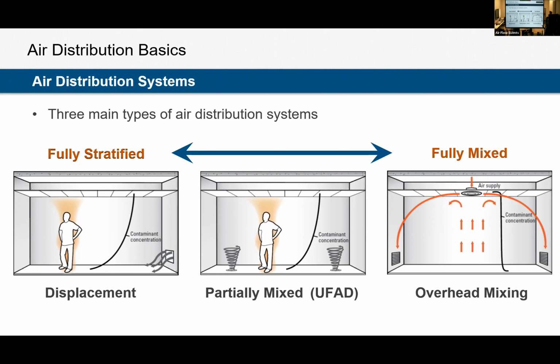The opposite type of system would be a stratified system. In a stratified system, air is moving in one direction through the space and there is zero mixing. If you've ever heard of displacement ventilation, this is that type of system. We're going to deliver air usually at the ground level. Our return is at the ceiling, and air is going to travel up through the space and out the exhaust. There is no mixing.